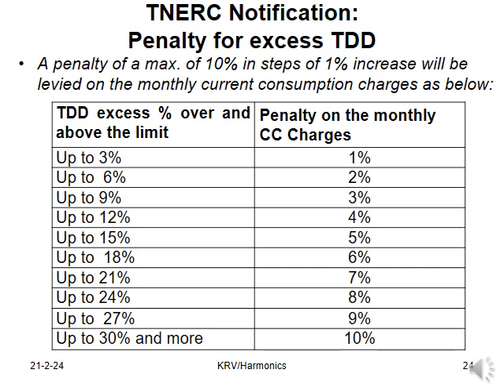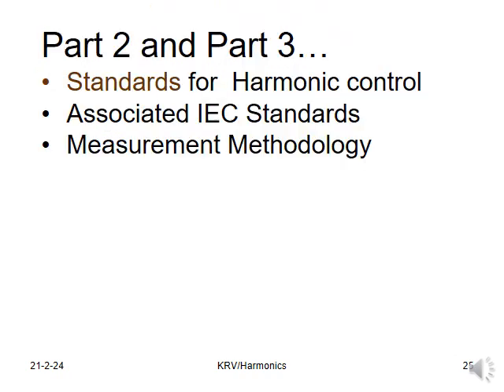The penalty for excess TDD is given in this table. A penalty of maximum 10%, in steps of 1% increase, will be levied on the monthly current consumption charges. Up to 3% in excess of the limits, the penalty is 1%. Up to 6%, the penalty is 2%. Up to 9%, the penalty is 3%, and so on. So, the maximum penalty is 10%. In part 2 and part 3 of this sequence, we will see the standards for harmonic control and the associated IEC standards, and measurement methodology in detail.